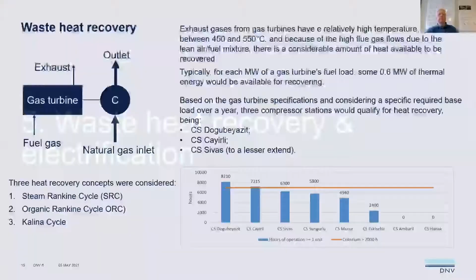For recovering waste heat from exhaust systems, sufficient heat over a year has to be available for justifying the associated investments. As a rule of thumb, heat recovery systems should be able to operate at full load during 80% of the time. This, of course, depends on the capacity of the heat recovery system and the deployment of the compressor station. The former rule of thumb implies that only part of the available heat can be recovered. The capacity of the heat recovery system is to be adjusted to the load duration of the compressor station. Eventually, based on their load duration, 3 compressor stations qualified for heat recovery, being Dogubeyazit, Cayirli, and Sivas.